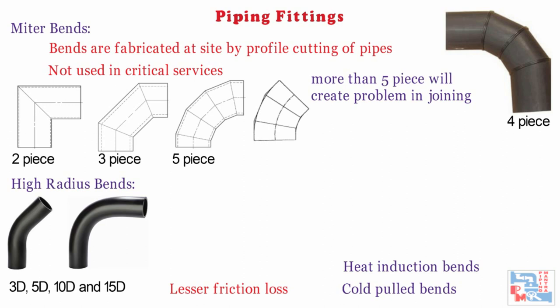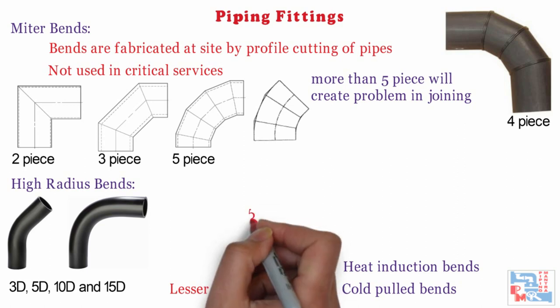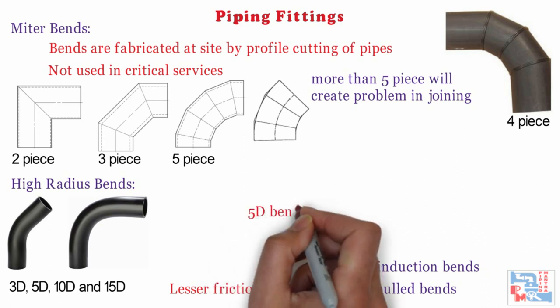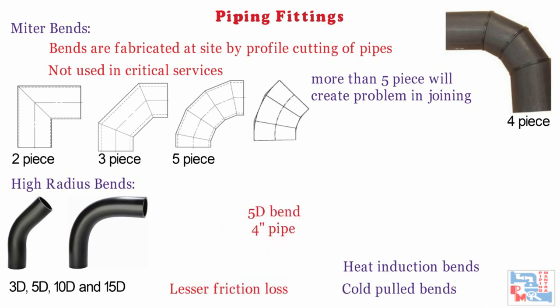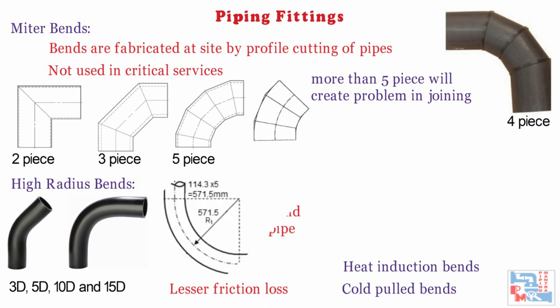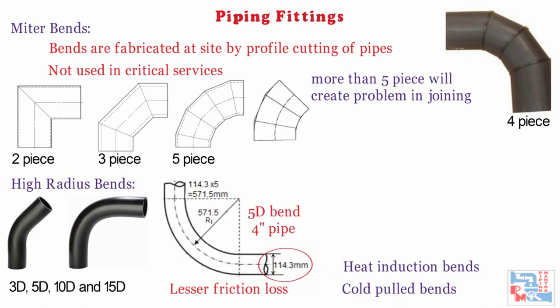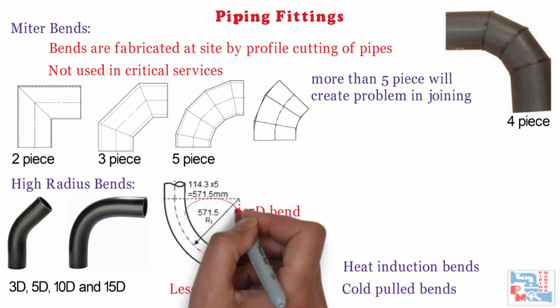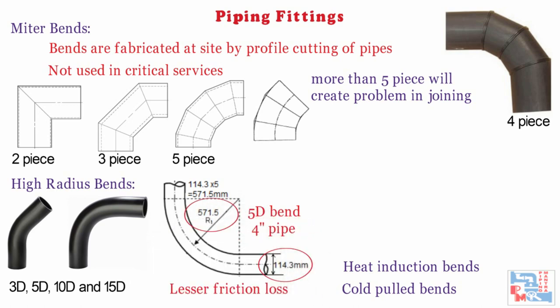Let's understand this better using an example. Let's calculate the radius of a 5D bend for a 4-inch pipe. It would be 5 times the OD of the pipe, which is 114.3 mm for a 4-inch pipe. So the radius would be 114.3 × 5, that is 571.5 mm.